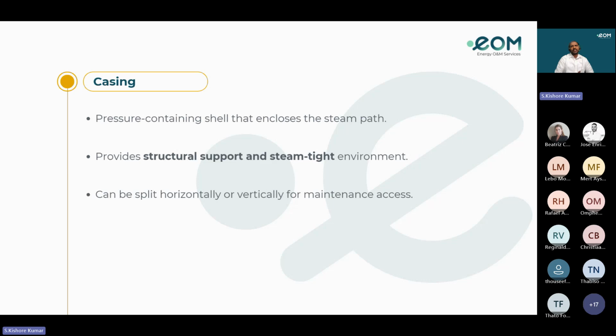So the steam turbine casing is the outer shell or enclosure that houses the turbine internals, rotor, blades, and diaphragms, and also contains and directs the flow of high pressure steam. The casing maintains structural integrity under high pressure and temperature, and it ensures safe operation by withstanding mechanical and thermal stresses. The main functions of the casing are pressure containment, steam flow control, mechanical support, and a safety barrier, with features like inlet and exhaust ports to control steam entry or exit, and also flanges and bolting for assembly and tight sealing. Insulation cladding minimizes heat loss and protects personnel. Different types of casings are there, like split casing, horizontal and welded casing, or barrel type casings.